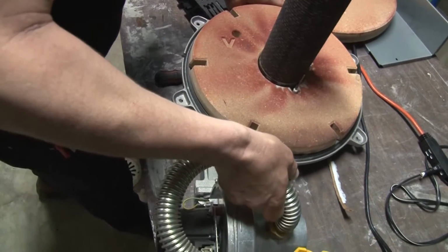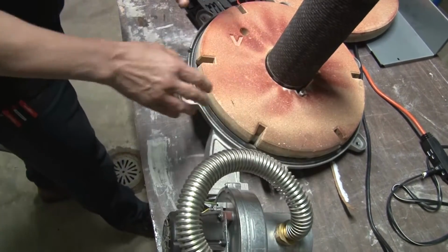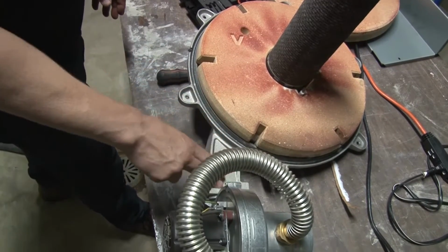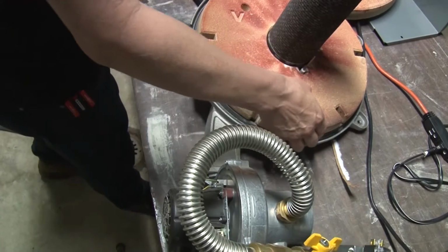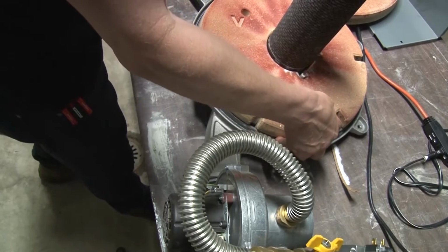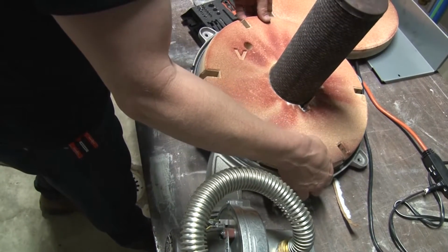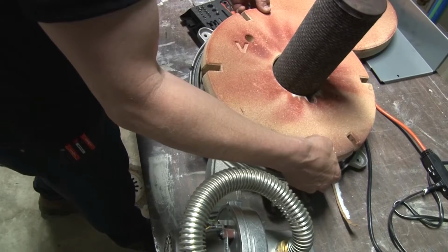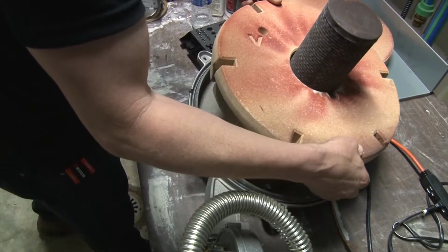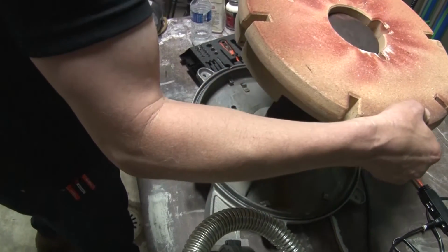But there is one area that we'll look at here. So I'm going to show you that. And I'm also going to show you there's a flapper that sits in that combustion air area as well we want to inspect before we put the burner back together. And I'll explain what that little flapper does in a second. So I already took the bolts out just to kind of speed it up a little bit.